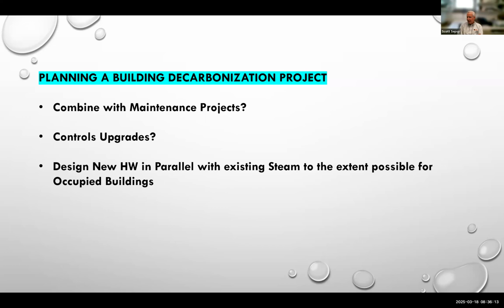Again, it's not all or nothing. Key areas might be paralleled with other systems offline longer for demo, then build sequence. When the building is commissioned and running on hot water, then you can demo the steam equipment and recover the space that was used by the steam equipment. We're finding that many of our converted mechanical rooms have lots of floor space and seem empty, actually, sometimes. Obviously, parallel systems are not necessary if a building is offline, for example, a dormitory that's unoccupied for the entire summer.